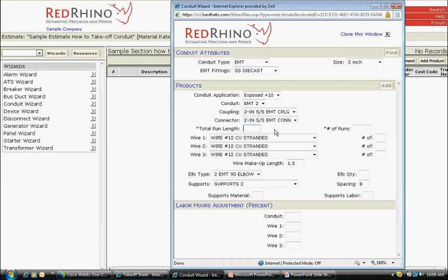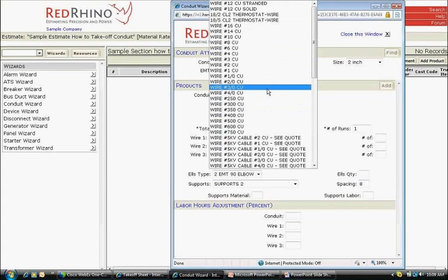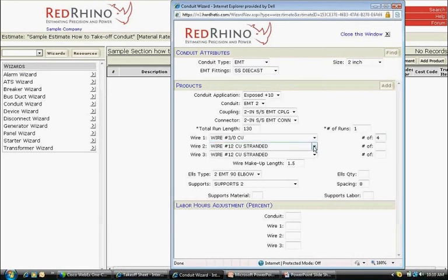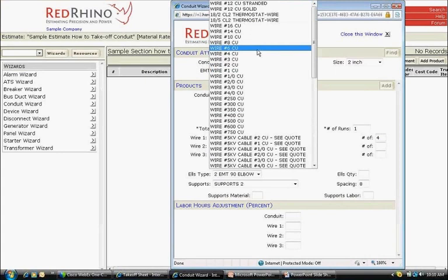Next, I click in the Total Run Length. I click in the Total Run Length box and type in 130 for the number of feet as shown on the takeoff sheet. Next to the right, I click on the Number of Runs box and type in 1 for 1 run. Next, I enter the 4 3-0 copper wires plus 1 number 6 ground. I click the top wire drop-down that says wire number 12 CU and select wire number 3-0 copper or CU for number 3-0 copper. To the right of that box, I click in the box that says number 4 for 4 conductors.